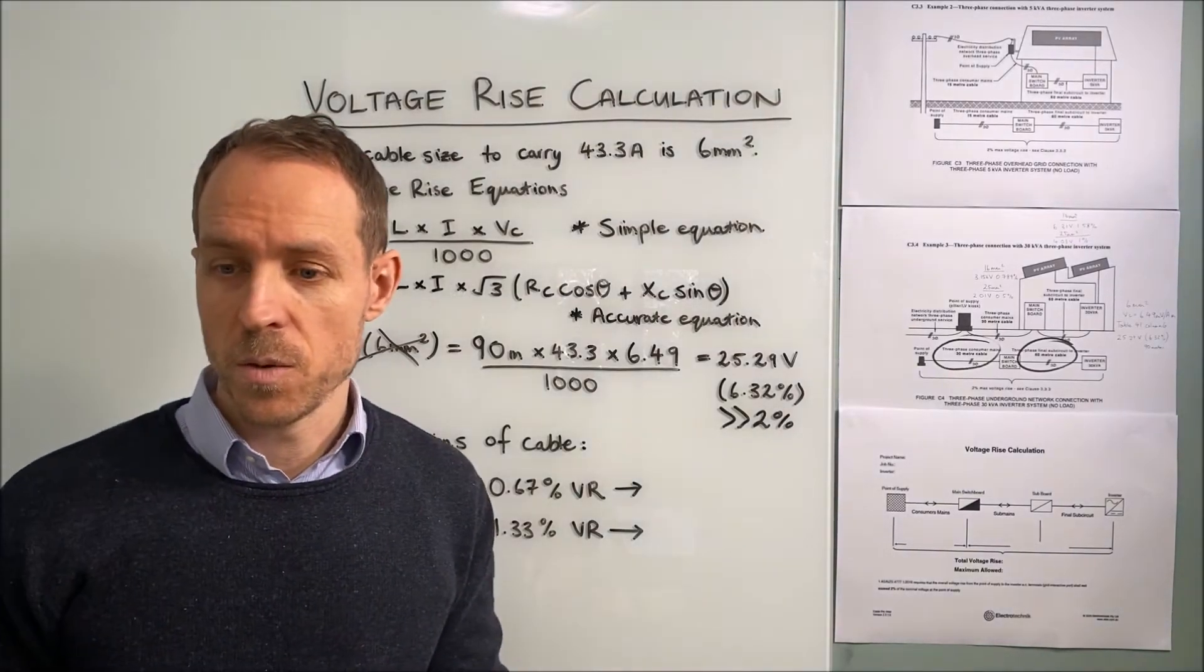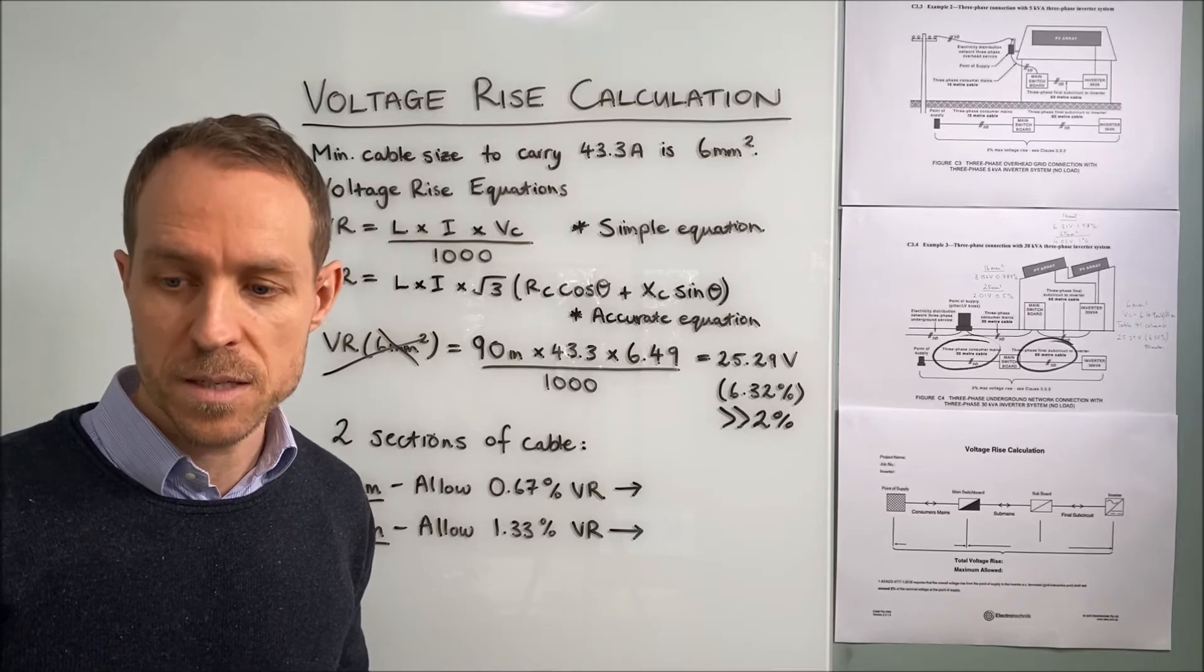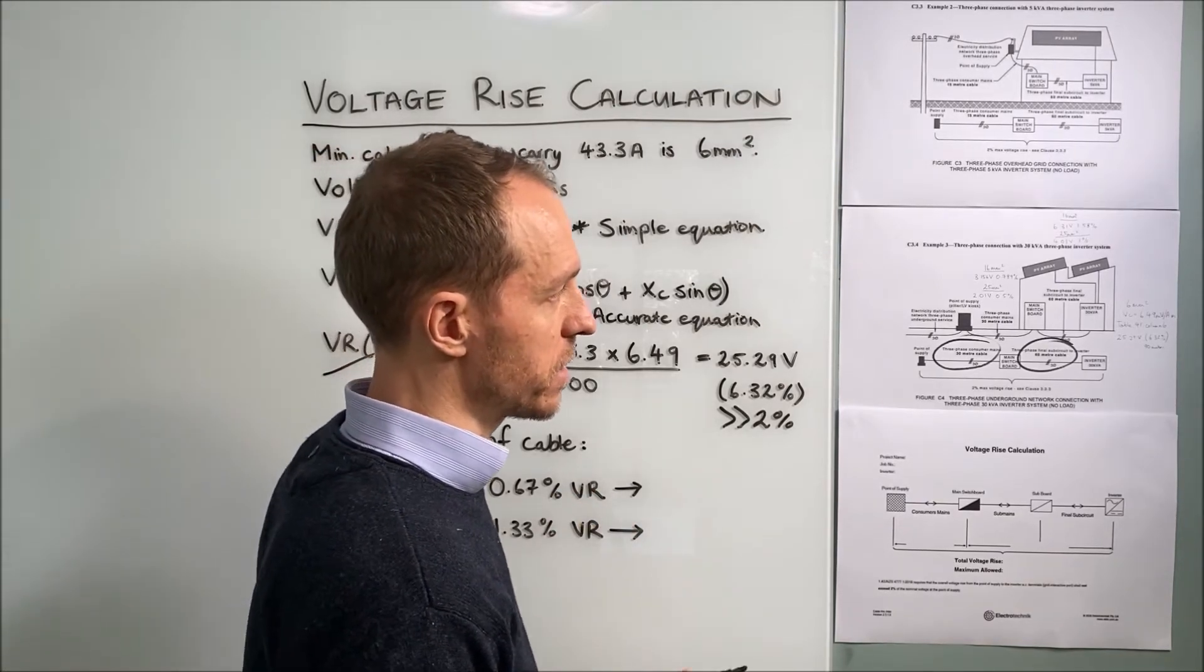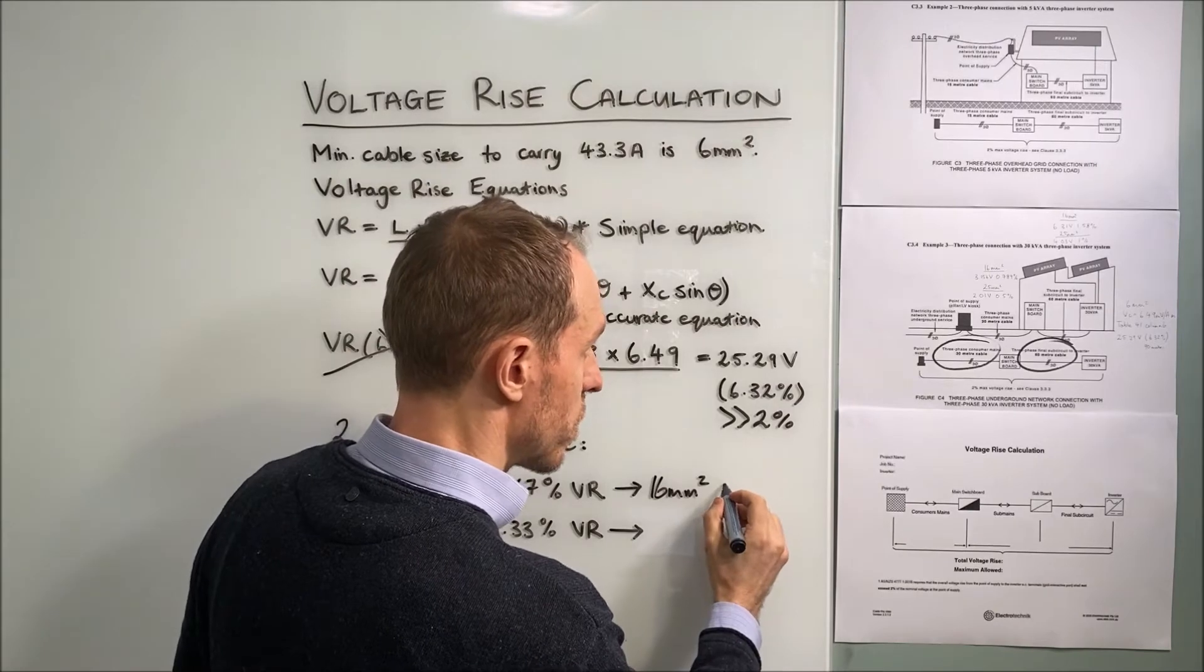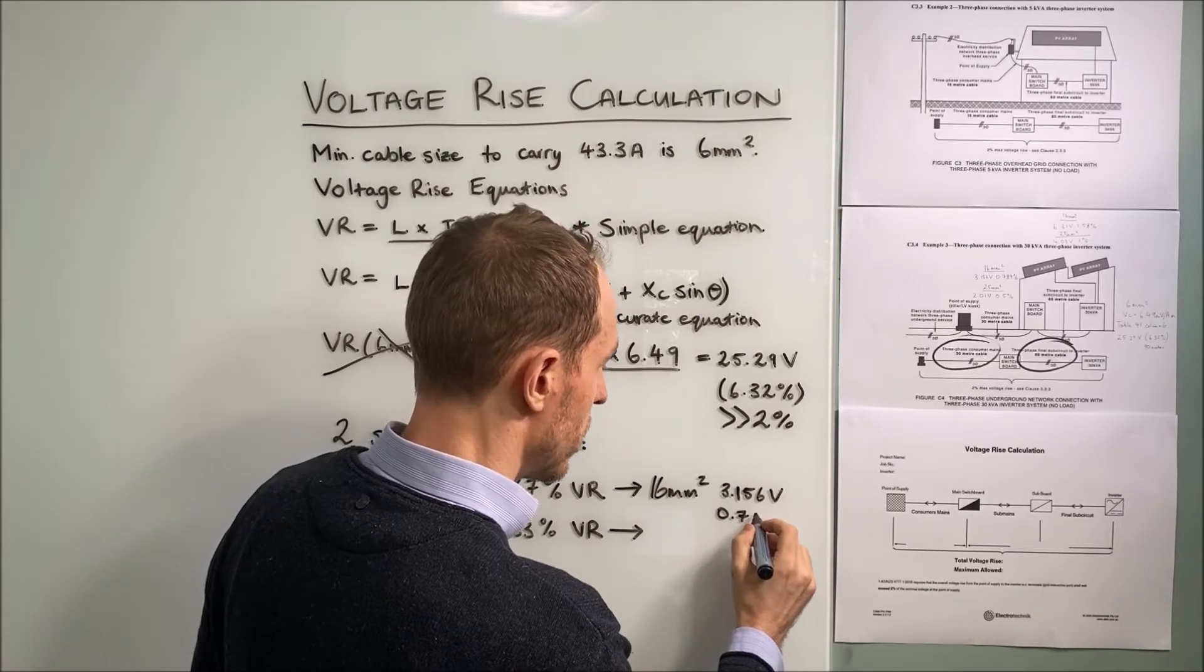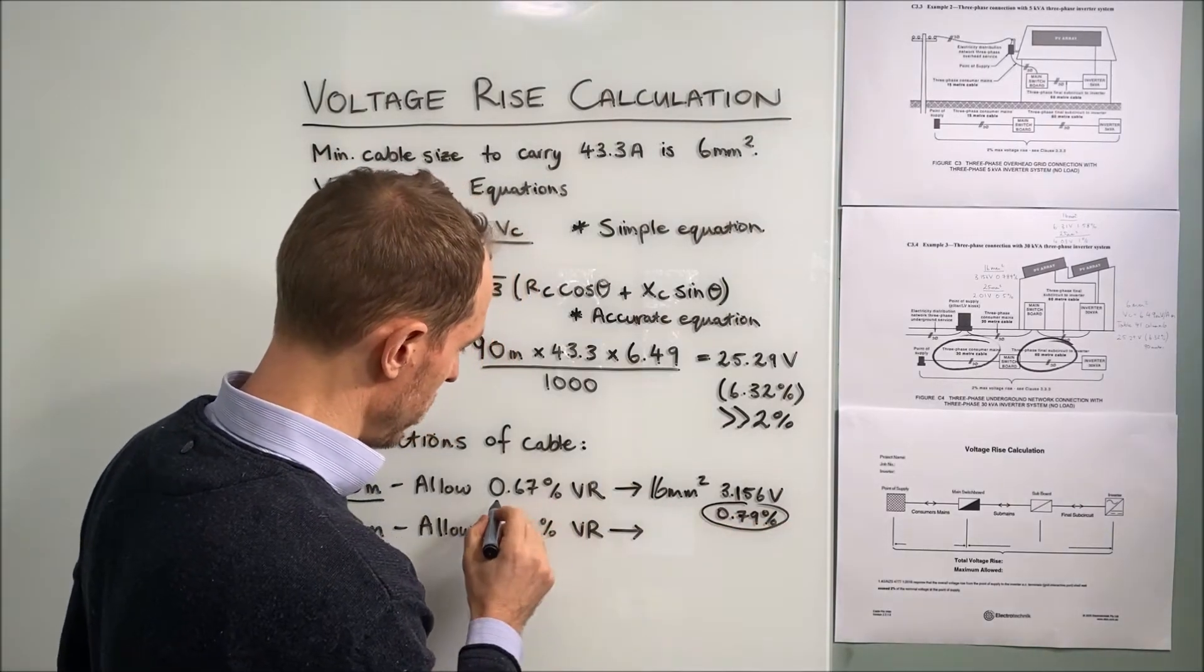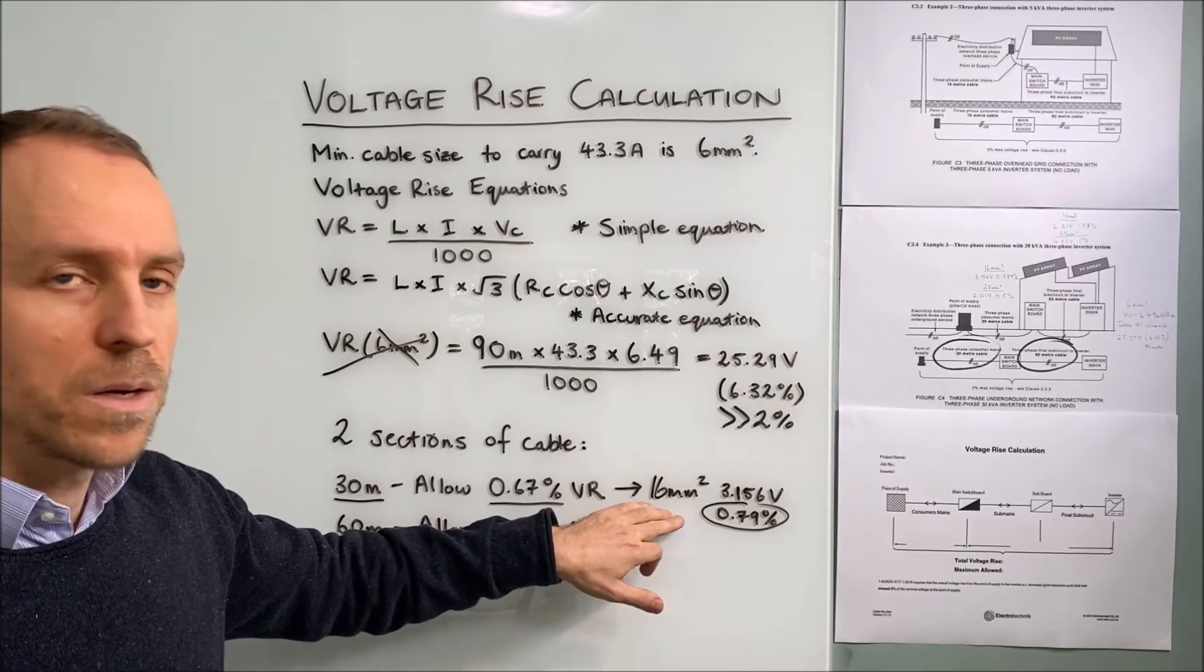Now we've done the calculations already. I'll show you what results we get for firstly say a 16 square millimeters which is much larger than our 6 square millimeters. So we have to go through quite a few iterations by hand to get to this. Now our voltage rise result for 16 square millimeters was 3.156 volts or 0.79%. Using a simple voltage rise equation for 16 square millimeters. Now this 0.79 is larger than 0.67 so 16 square millimeters is not going to meet our voltage rise requirement for that first section.